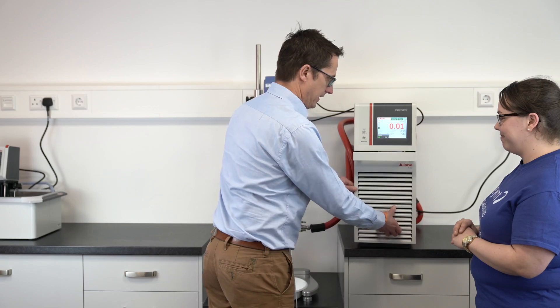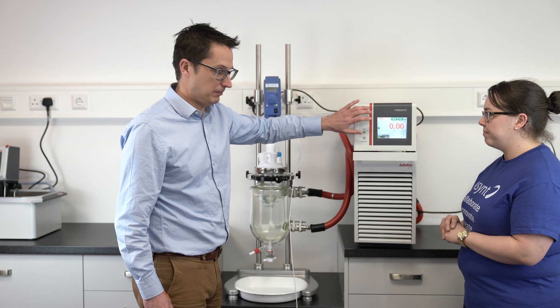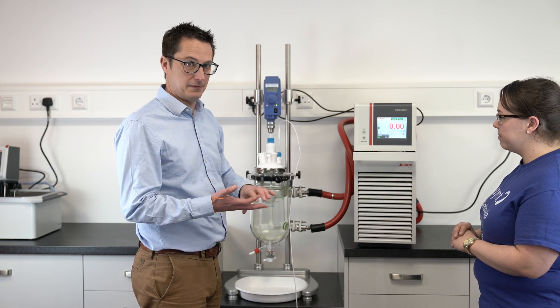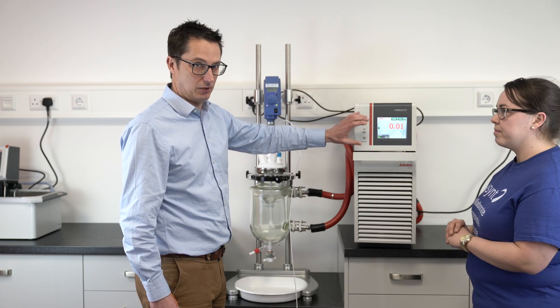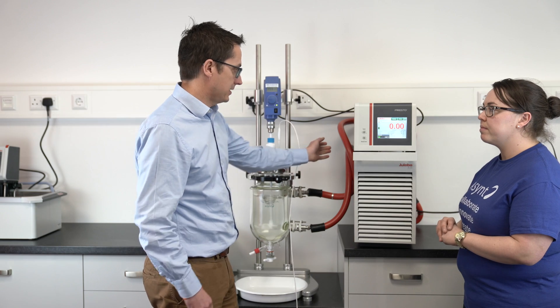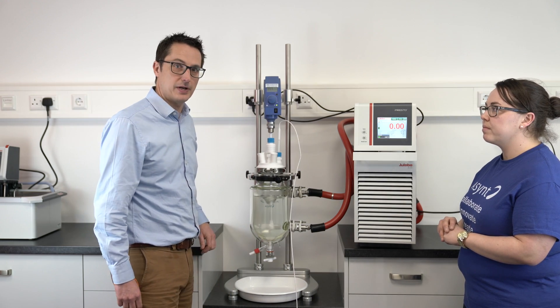The fourth reason is the unit is controlled by this Windows CE computer here, complete with our software. Every single parameter is available from here — from the PIDs, from the temperature settings — and you have the ability to log all of that data on USB, SD data card, or output through RS232. And finally, like all Prestos, it has built-in pressure control so that you never have a risk of breaking your glass reactor.